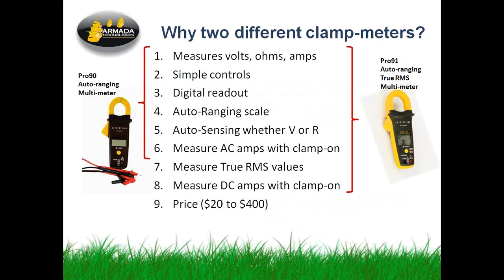You can measure the power in household electrical circuits for that matter, as long as you can get around the wire. But in the case of the Pro91, you see the feature set has expanded a little bit, and we're able to use the Pro91 in LED lighting systems where true RMS features are required. True RMS is a term that's pretty geeky. It stands for root mean squared, RMS. What it really means is that this meter is computing, and no matter what kind of waveform and off and on sequence is going on in the lighting system, it will measure accurately. And in LED systems, that's very important because the current is not linear, and it needs to be measured a little differently. This also measures DC amps through the clamp meter. The place I would see that as having some extra benefit is in solar powering systems where the feed from the solar panel is solid DC, and you need to measure that before it gets to the inverter.